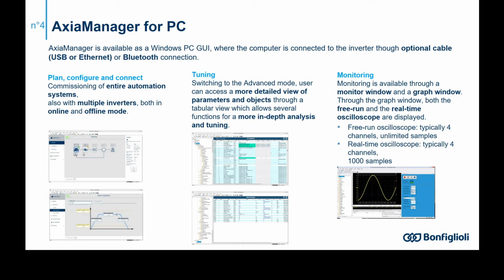In some cases, we want to see in the time layer quicker than 1 millisecond, an example when it comes to current controller settings. For this, the real-time oscilloscope gives us exactly this possibility. All scope functions, of course, offer trigger possibilities and a wide range of selections as a source for the different channels. The scope offers support for multiple channels, making the diagnosis easy and flexible.